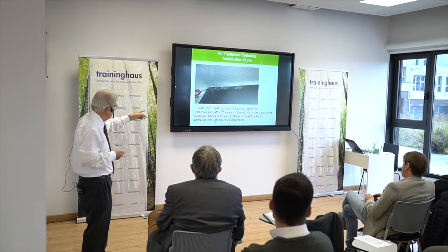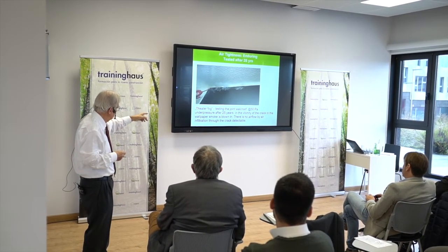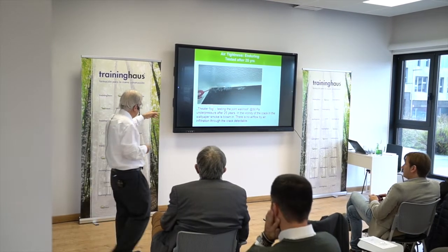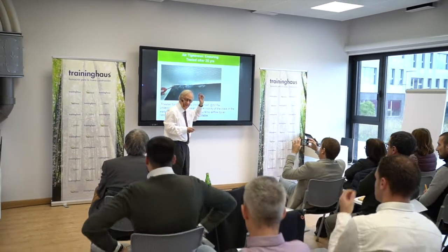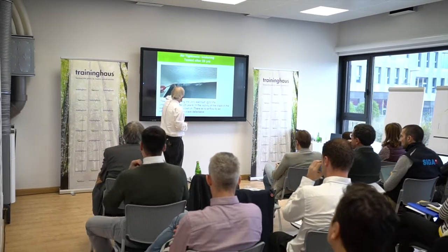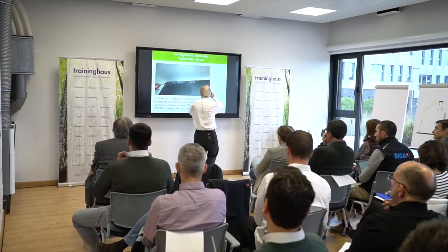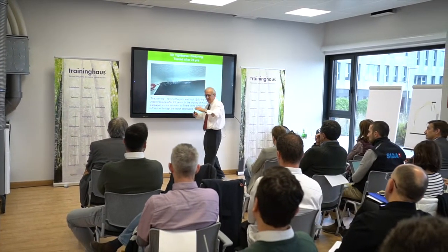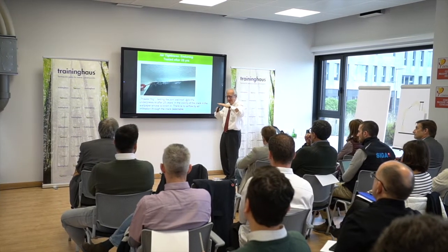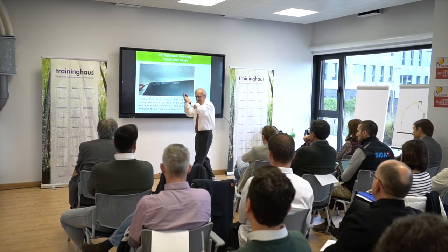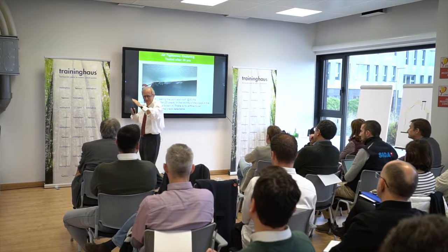This is a measurement done with a theater fog after about 25 years, and you see there is no driven movement of that fog. And what you also see here is, of course, there is a crack in the plaster. So it wouldn't work without this airtight layer. It's not enough to just have a plaster connecting the wall to the roof.